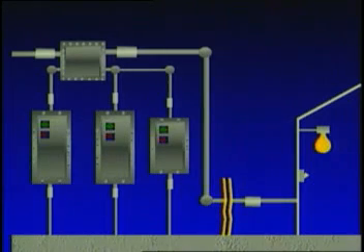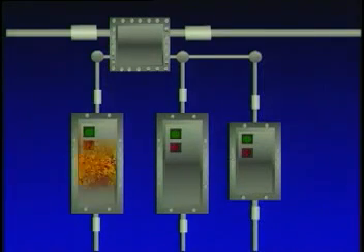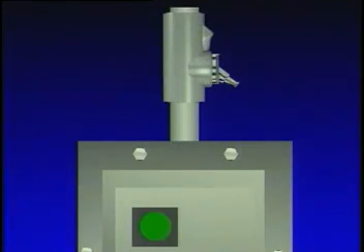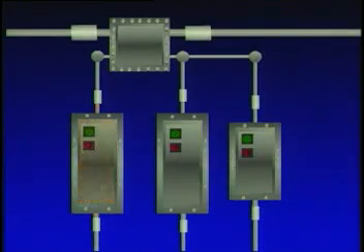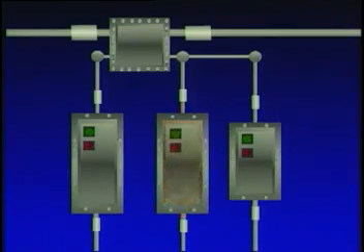To understand the importance of a properly installed seal, it may help to review the construction of explosion-proof electrical systems. When an explosion occurs inside an explosion-proof electrical system, the burning gases resulting from the explosion must be confined to the interior of this system to prevent ignition of the surrounding atmosphere. The components of the electrical system are designed and constructed to withstand the maximum pressures generated by these internal explosions.